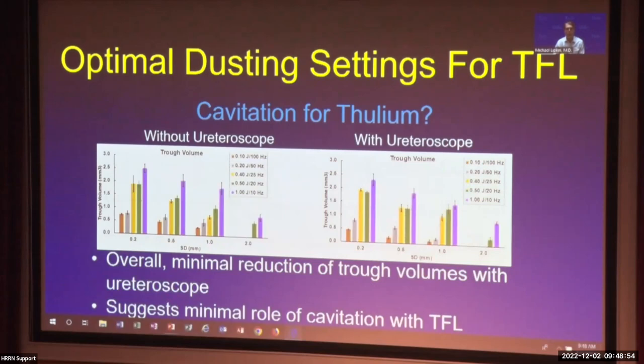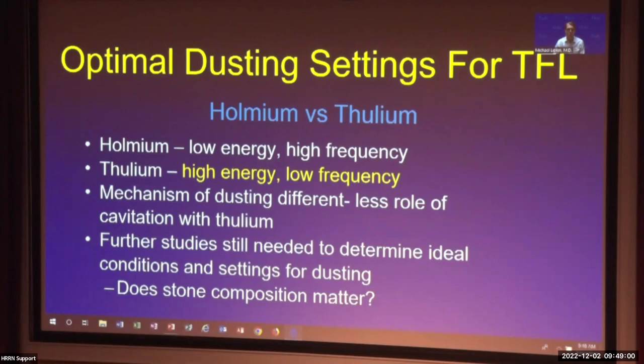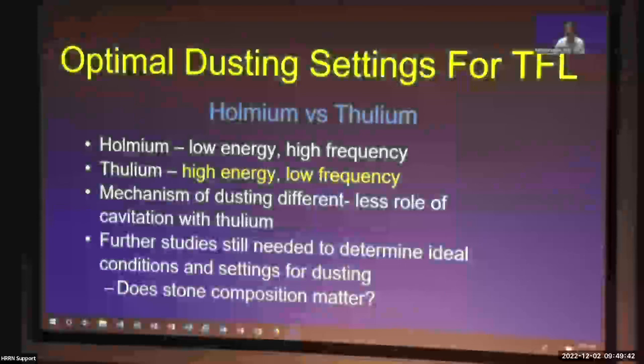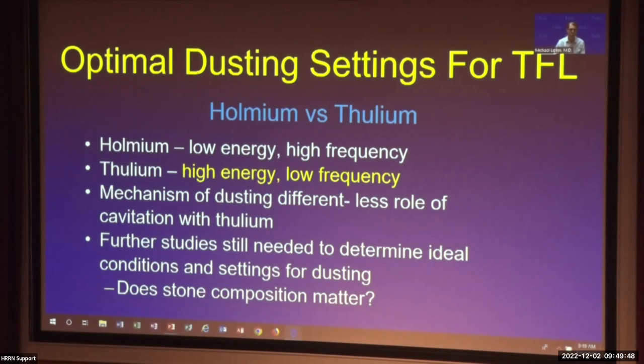In conclusion, what are the optimal dusting settings? For holmium: low energy, high frequency, probably with a standoff distance of 0.5 mm. For thulium: high energy, low frequency, shorter pulse duration, in contact with the stone — with lower overall energy and lower risk of heat injury. This is likely due to the different mechanism of dusting, meaning less role of cavitation with thulium. Further studies are still needed to deduce the full mechanism for thulium. Key outstanding questions include which laser is better for which stone composition, and whether settings vary based on stone composition. Thank you for the opportunity to present.